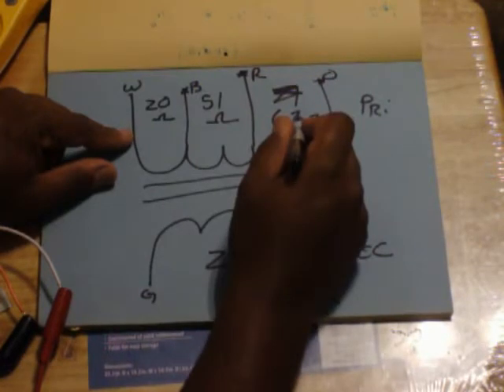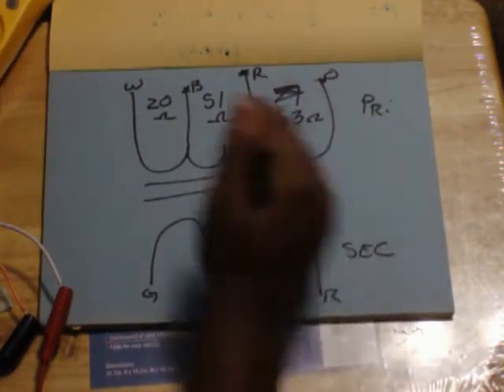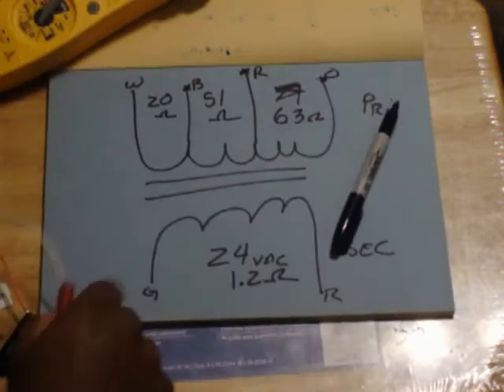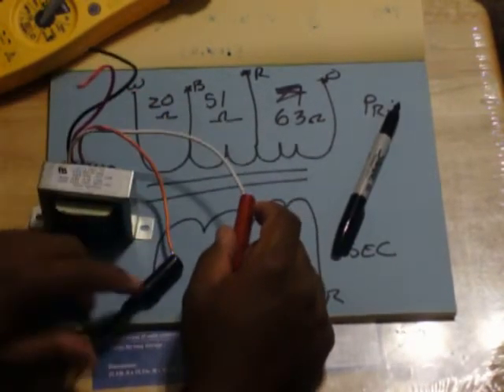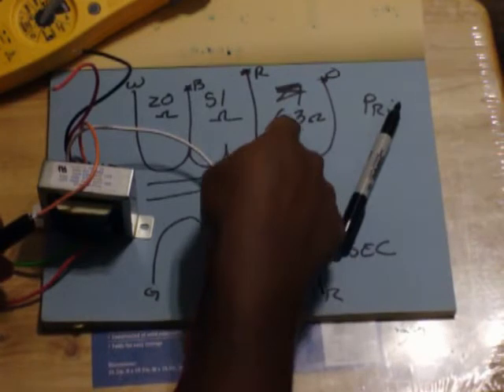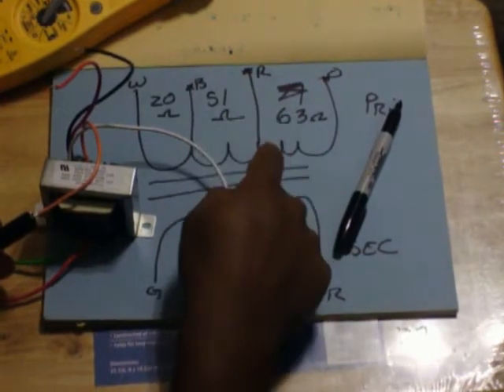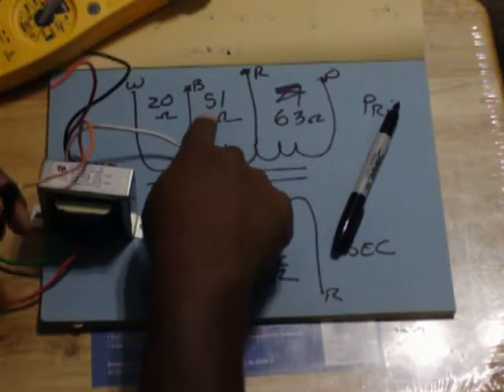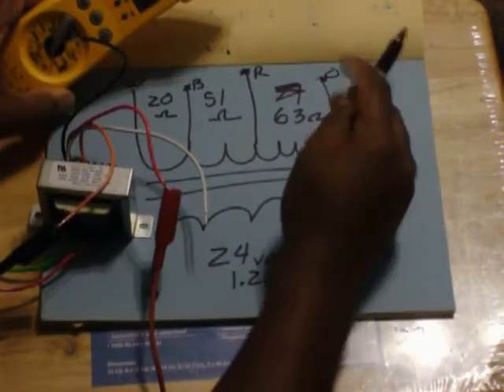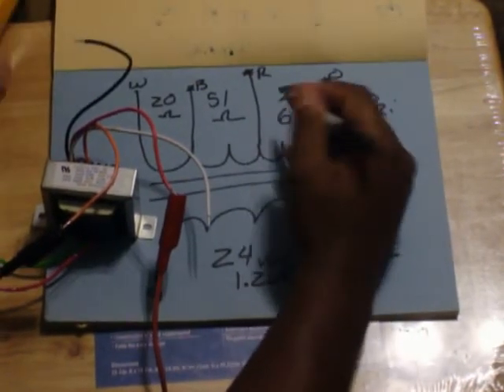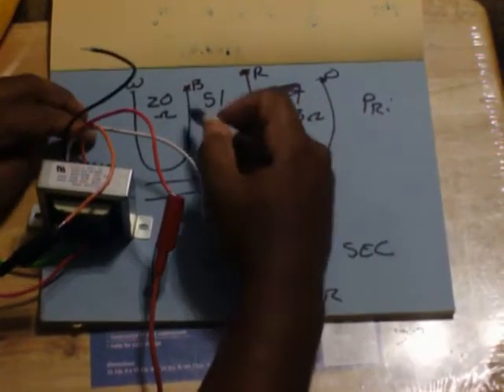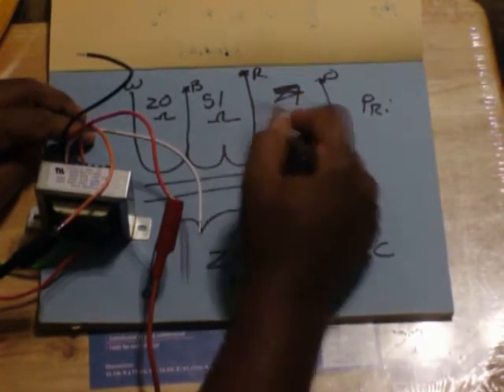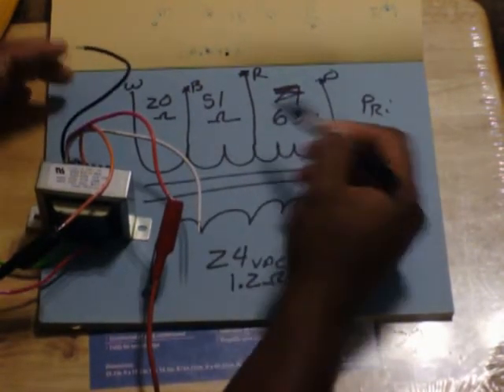So let's just say 50 plus 20, so that's 70, 130 total. So we went from white to orange, we should get all of them. We could break it down between red and orange. So if we had 51 here, that's an extra 14, so let's try red and orange. 13 ohms. So you can see how we can pick that up. If you had from here to here 51, and then from here to here 63, you picked up another 12, 13 ohms, you can ohm them out individually and get it.